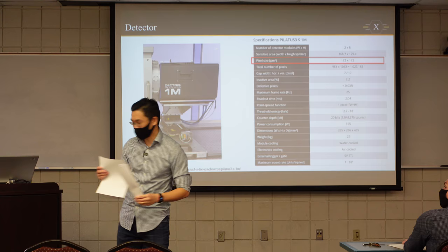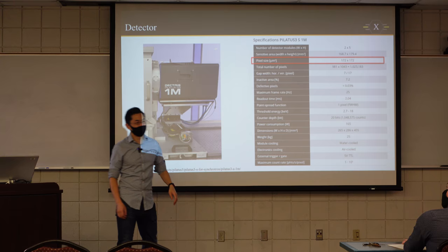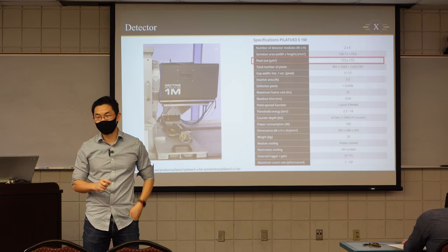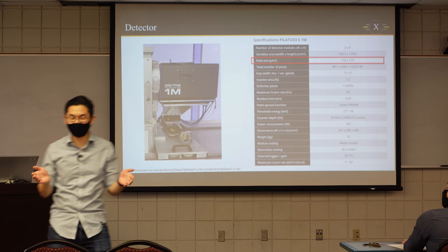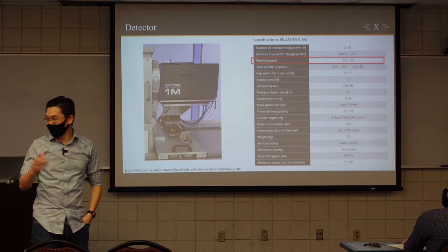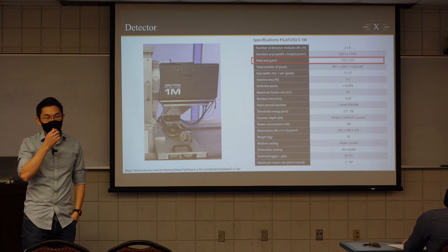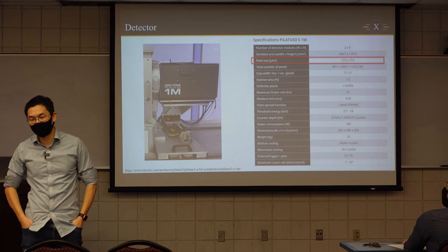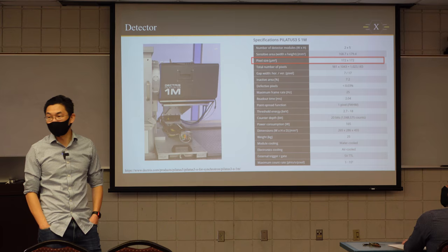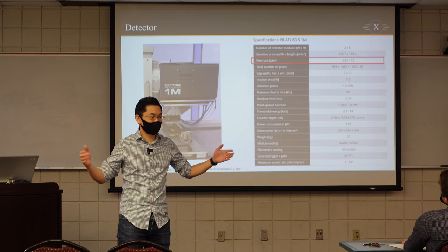You know what, this reminds me actually how people market their engines in, for example, cars and vehicles. They like to put a large badge on there, like in outboard, they like to put 250 there, just to tell you this is 250 horsepower. This one just tells you this is a nice large detector. And the latest technology, they can go even bigger. In both pixel, 4M means there's 4 million pixels, but the detector area is not four times bigger because they squeeze more pixels in the area, better resolution. So that one costs also more than what we have. So hopefully down the road we can upgrade to a bigger detector that helps to measure the resolution.